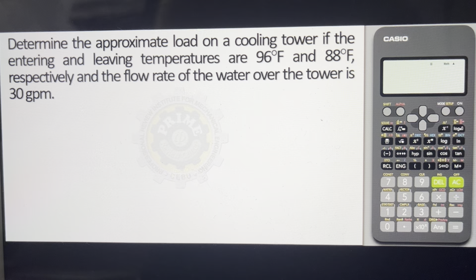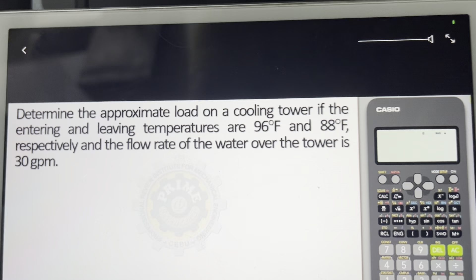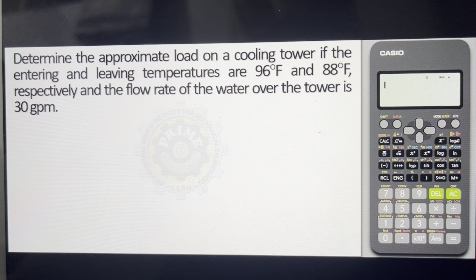Okay, sample problem: determine the approximate load on the cooling tower if the entering and leaving temperatures are 96 and 88 respectively, and the flow of water is 30 GPM. So water ang sinabi dito, entrance and exit. So kung tubig yan, ang load niya ay mabilis lang, MC delta T. Pero pag cooling tower, since water yung load natin, meron tayong shortcut.